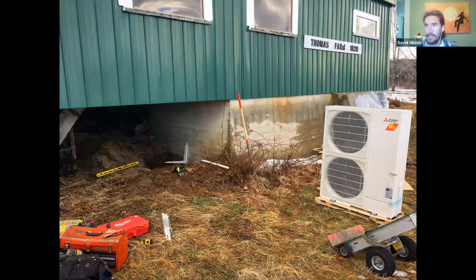And so for our compressor, we actually have a sheltered area under the barn that's open to outside. It needs to have full circulation around it for the outside air to exchange heat with, but it's sheltered with a rock wall on one side and a concrete wall on another side. And then it's under the barn, so there's no risk of snow or ice sliding down onto it. And so our unit, you can see one of the brackets is hung on the concrete wall there. It did take a little bit of digging down to have enough space underneath it, but that was the best space in our house. But often they'll just be mounted to the outside of the house.